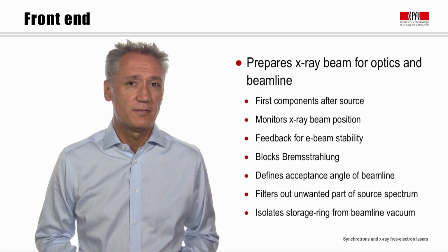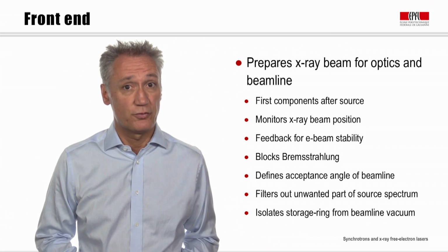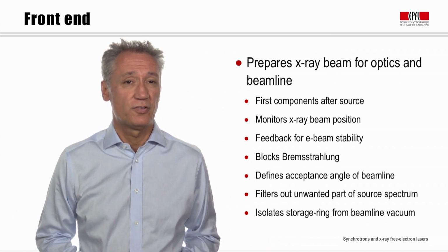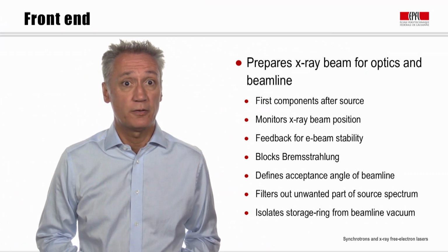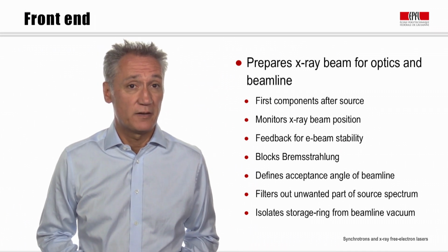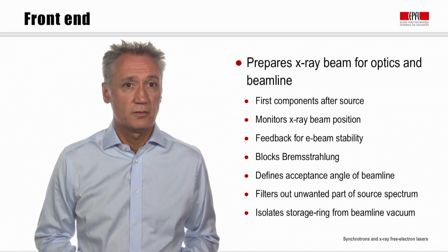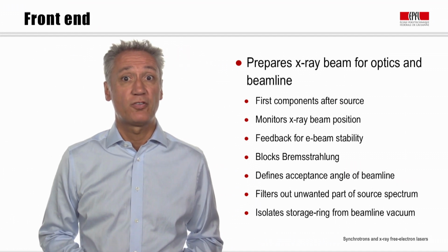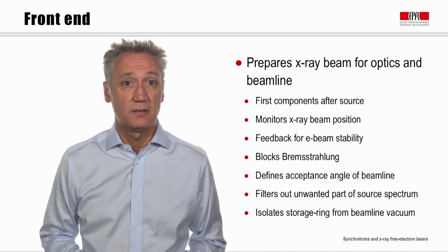In most cases, very high energy gamma radiation up to the energy of the electrons within the storage ring is produced as an inevitable consequence of the electrons occasionally colliding with residual gas molecules that remain even at pressures as low as 10 to the minus 10 millibars. This radiation, although only generating a total power measured in a few tens of milliwatts throughout the entire facility, is highly ionizing and must be blocked.